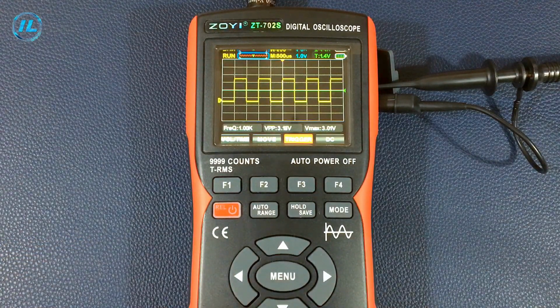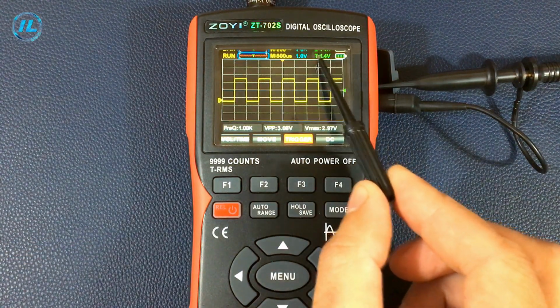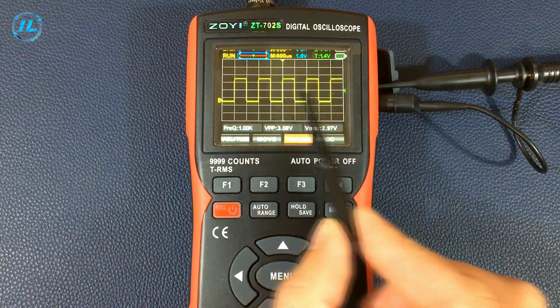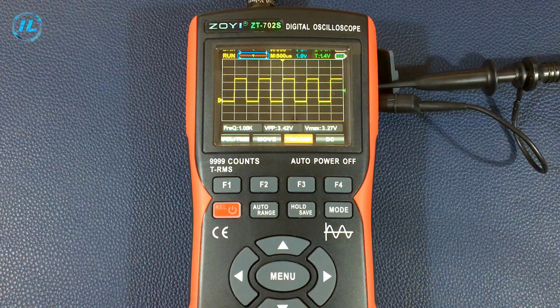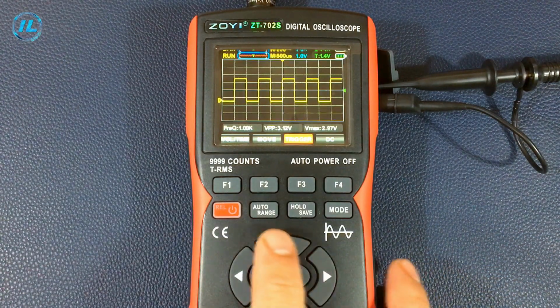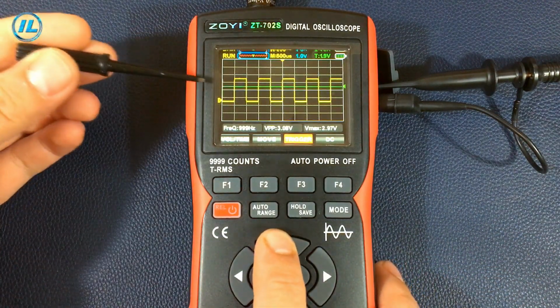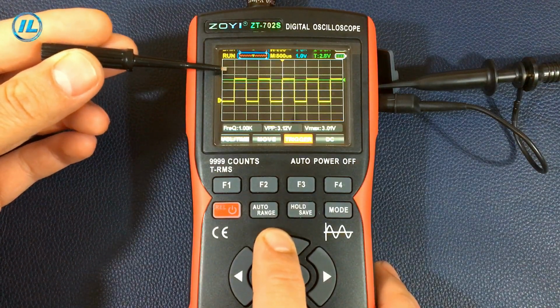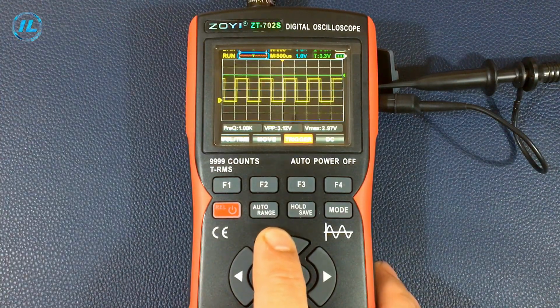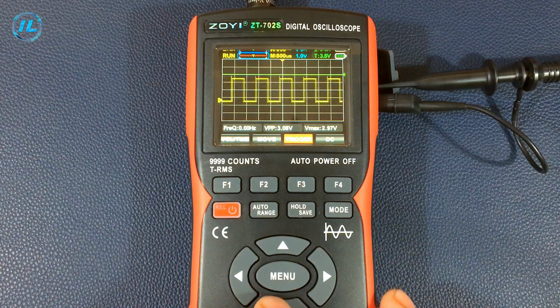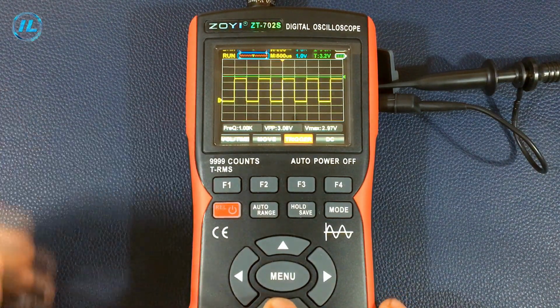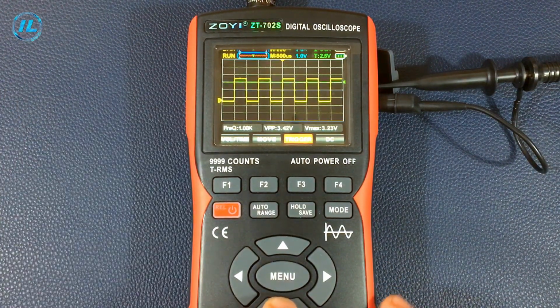The F3 button is a trigger. Now we can change the synchronization voltage, which is indicated here at the top of the screen and is also indicated by this green stripe. This strip can be moved with arrows. When it goes beyond the waveform, synchronization is disrupted. When the strip returns to the waveform area, synchronization is restored.